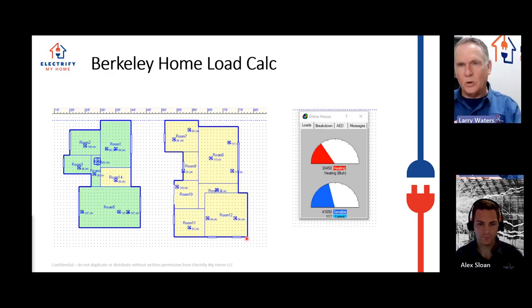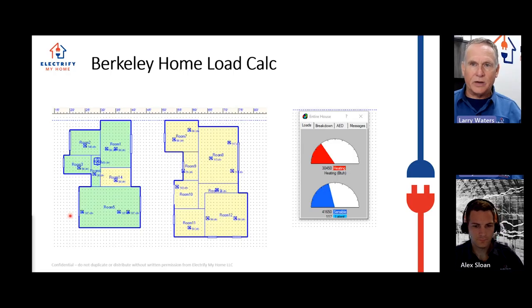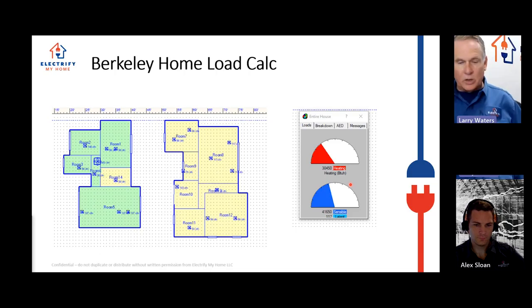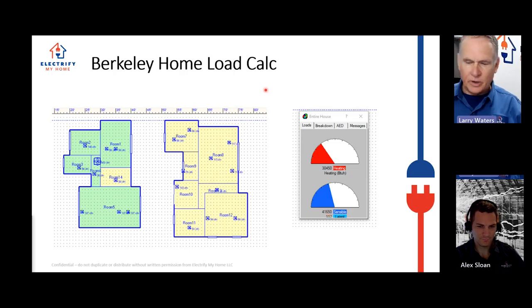The whole house was beautiful, but it was porous as all get out. It had really high infiltration, and it had all these south-facing windows and the big door here, and all these south-facing windows on the top floor. And it actually came out that it had a higher load on cooling than heating. And you'll notice my latent load is super low.